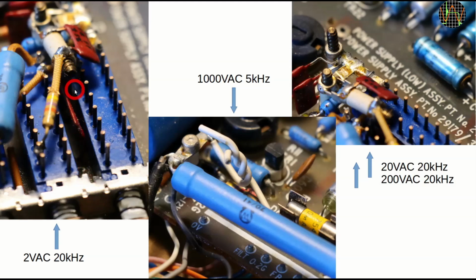The trimmer caps for the 20 volts and 200 volts can really only be operated once the meter is together, because you have to go through a hole on the top of the PCB to reach the screw. The other side you see here has no slots, so these trimmers can't be operated while the meter is disassembled. And then there is the trimmer cap for the 1000 volt range here. What trimmer cap, you may ask? That twisted piece of white wire is the trimmer. No, sorry, I'm not going to touch this and twist it a bit more or undo twists while 1000 volts are applied on that blue high voltage resistor in front of the white wire.